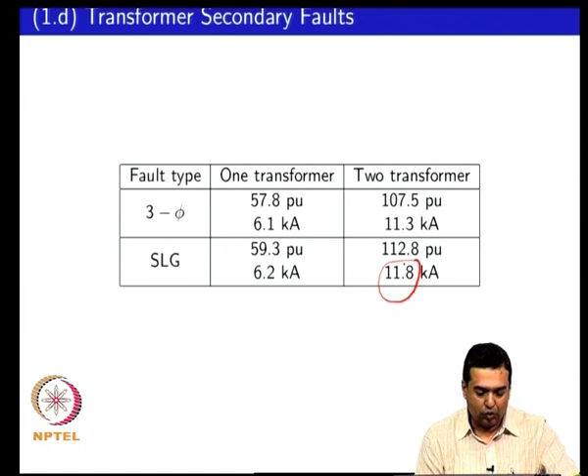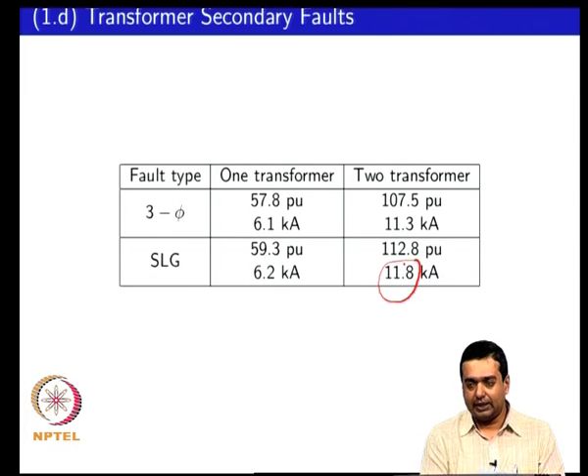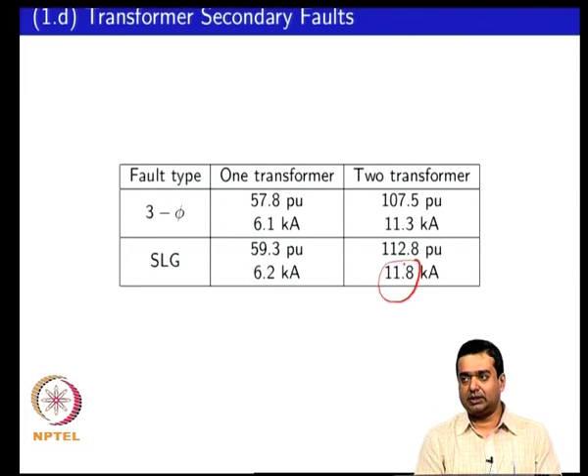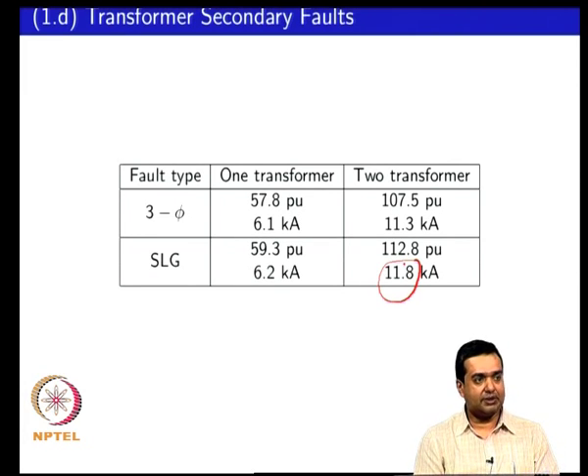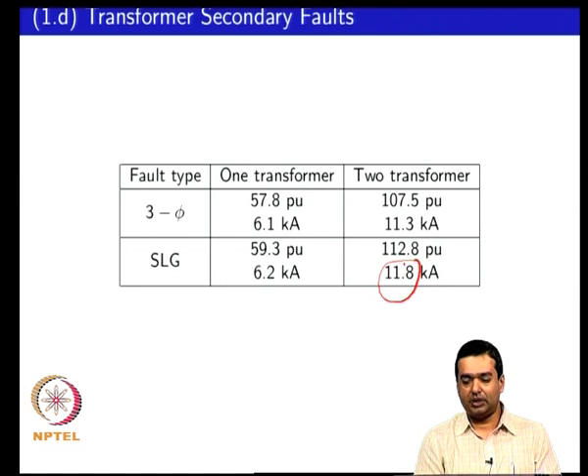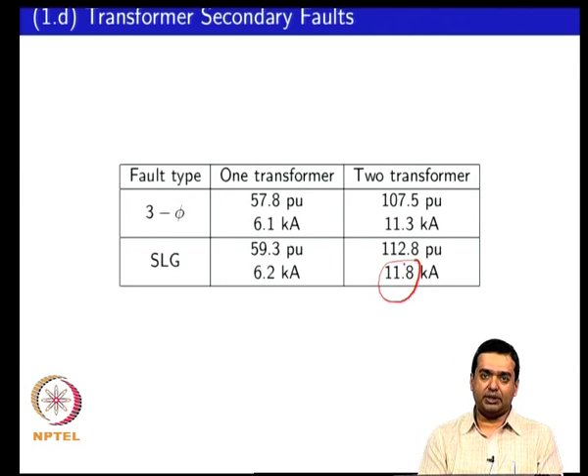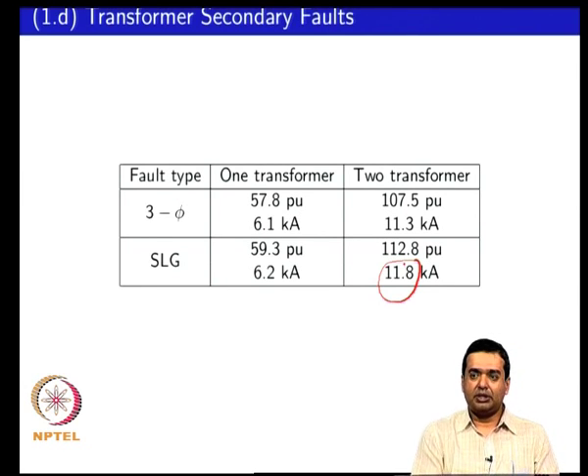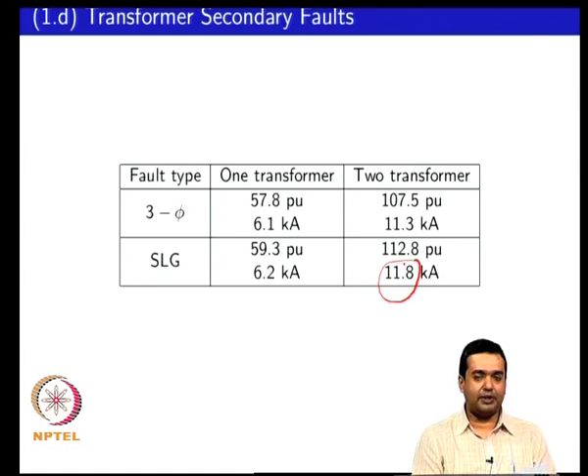The rated current of each feeder is 105 amps — that is the 2 MVA power level. So your breakers have to be rated for a continuous current level of 105 amps.